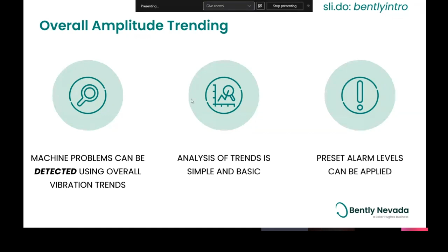So this is a simple trend plot. We've got a couple of parameters on here. In Bently Nevada hardware, typically we offer alert and danger set points. These are often recommended by OEMs or just from your past experience, knowing how your machines react. The alert is generally set to give you a heads up that something is getting really bad and that imminent danger or failure may be possible. The red is generally set as a protection set point. If it goes above that red line, you ideally want to shut the machine down very quickly. Otherwise, you run the risk of losing material, losing products, or even harming other people. And that's what we want to avoid.